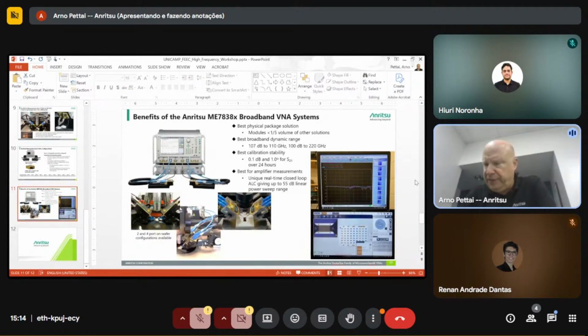So I'm just going to summarize briefly how we've addressed these challenges for measurements in the sub-terahertz range, having the modules that are not only high performance, but also small enough to be able to mount close to where we want to set our reference plane for the measurement is a key advantage. That, of course, eliminates additional losses and preserves dynamic range for the system. We have around 100 dB of dynamic range to 220, a little bit more up to 110.